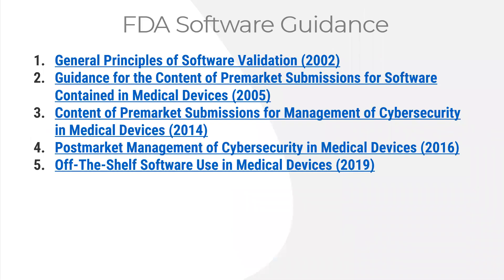The first thing you should be aware of if you're developing software as a medical device is that the FDA has already published a bunch of free guidance documents on what documentation is required for a 510(k) submission. The 510(k) is the most common pathway for about 80% of medical devices to get on the market in the US. I've provided hyperlinks to the five free guidance documents in the comments below, and if you're reading our blog post, you'll find those five hyperlinks there as well.